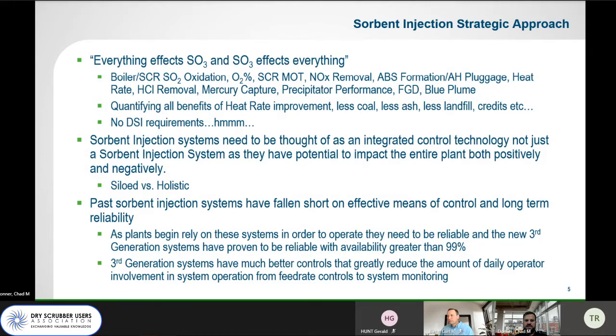Heat rate is dependent on SO3. HCl capture and removal with hydrated lime has an impact with SO3. Mercury capture is dependent on SO3. Precips operate off SO3. And then the emission of blue plume out the stack, SO3 has a role in FGD as well. So quantifying all the benefits for heat rate, when you look at all of the constituents between material handling of coal, ash, landfill, credits, etc., there can be significant benefits to improving heat rate by taking SO3 out and operating the back end or the cold end of your plant at lower temperatures.